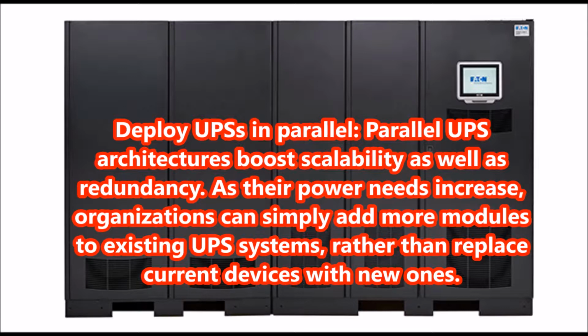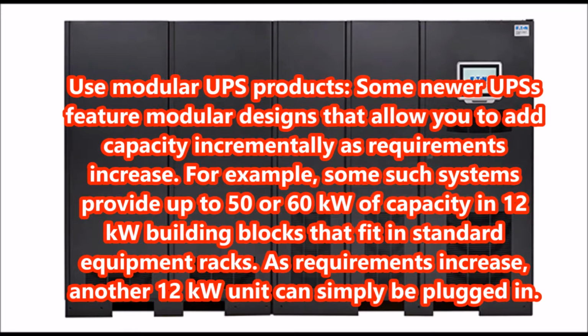As their power needs increase, organizations can simply add more modules to existing UPS systems, rather than replace current devices with new ones. Use modular UPS products. Some newer UPSs feature modular designs that allow you to add capacity incrementally as requirements increase. For example, some such systems provide up to 50 or 60 kilowatts of capacity in 12 kilowatt building blocks that fit in standard equipment racks. As requirements increase, another 12 kilowatt unit can simply be plugged in.